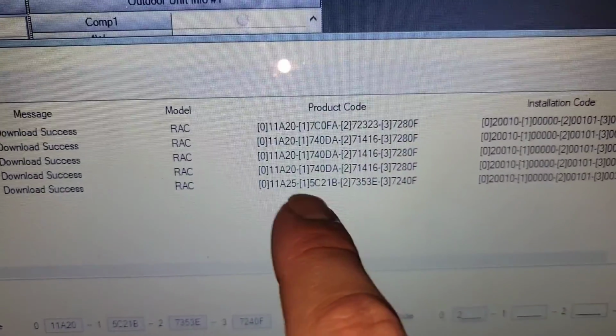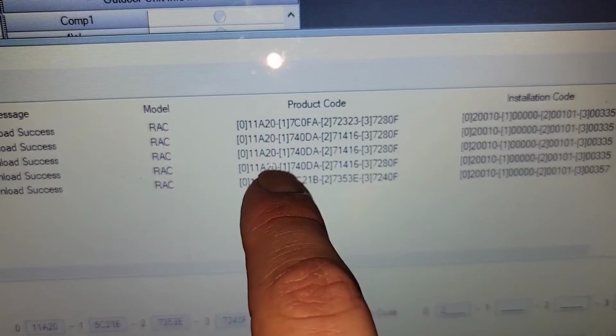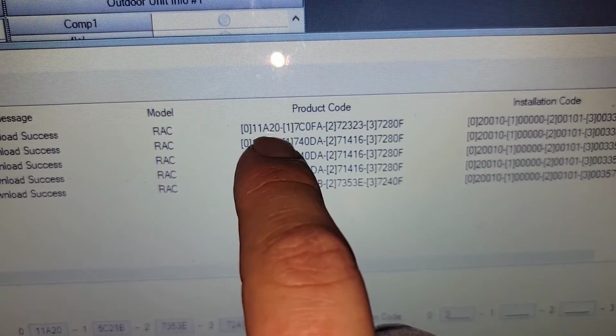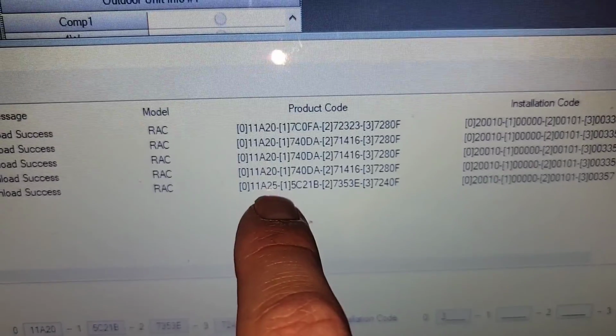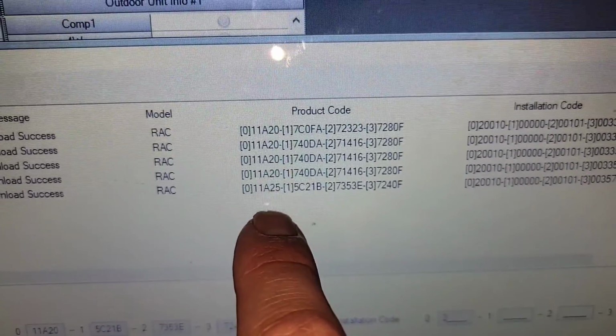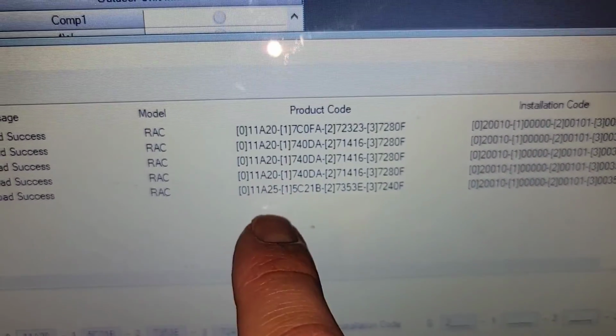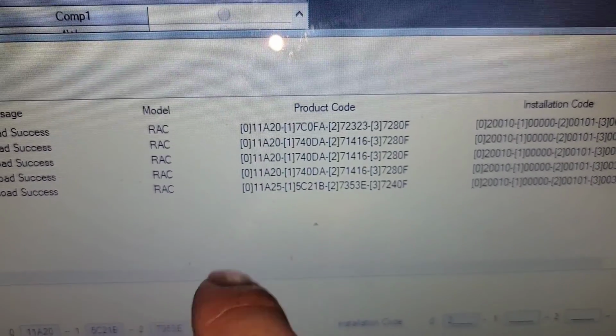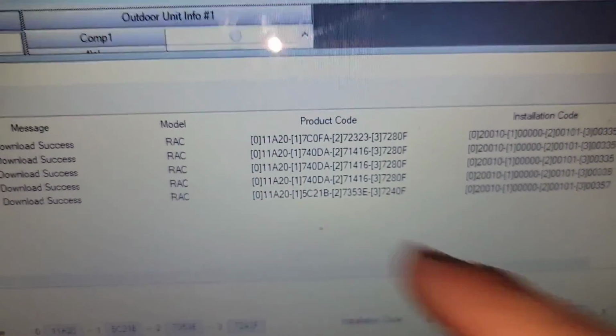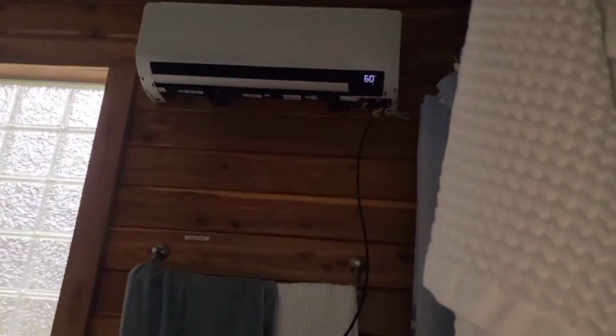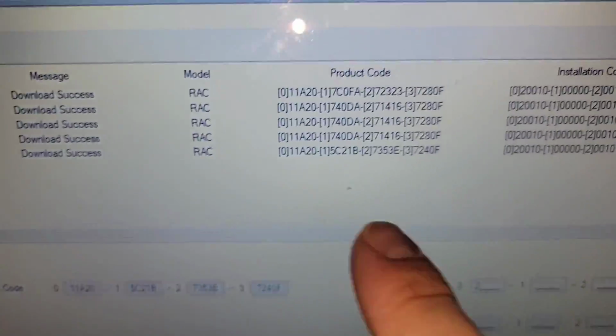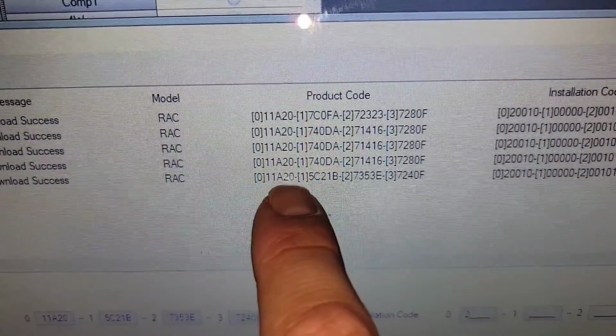So these are the 5 units. I just finished changing a product code, and I changed the 5 to a 0. You see how this one's still 5? It's going to be 0 here in a moment. This is taking out the heating compensation, because the indoor units were displaying a temperature lower than the actual temperature, so they were staying running. Now they will read the actual temperature. Look how that changed, see how that changed?